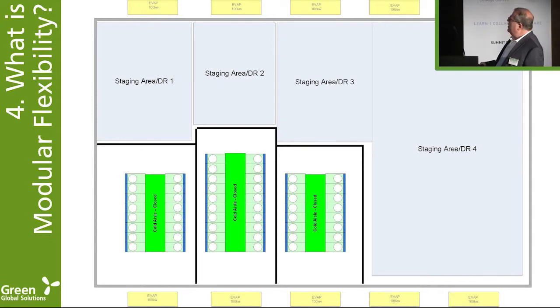What does it mean? It means my PUE is going to be maintained at a pretty good level. Okay, not maximum, but it won't be far off the best possible PUE, unlike the traditional design. So, because we don't have leakage, there's no air escaping under here. And here, we've only got vents in the cold aisle here. And otherwise, there's no air going anywhere else.